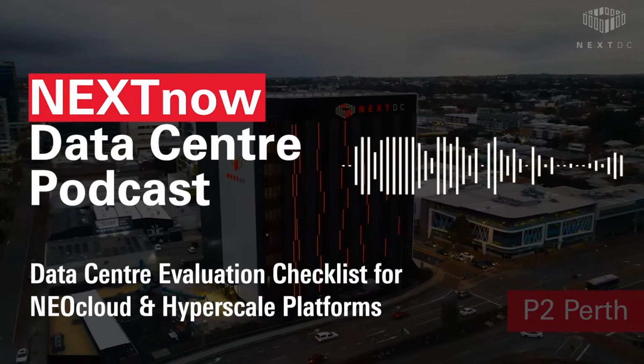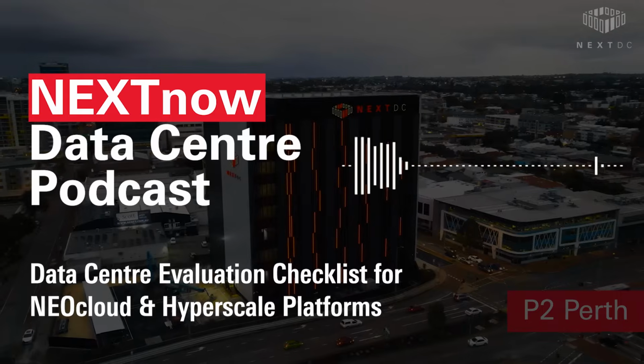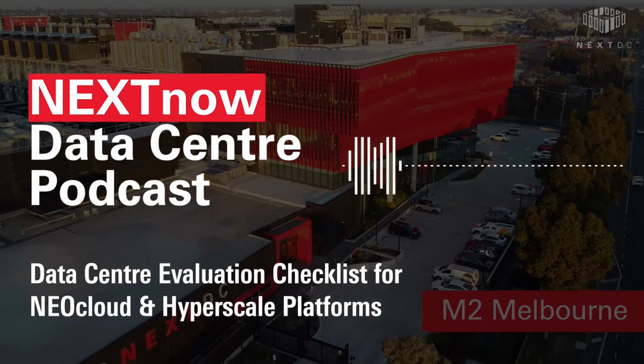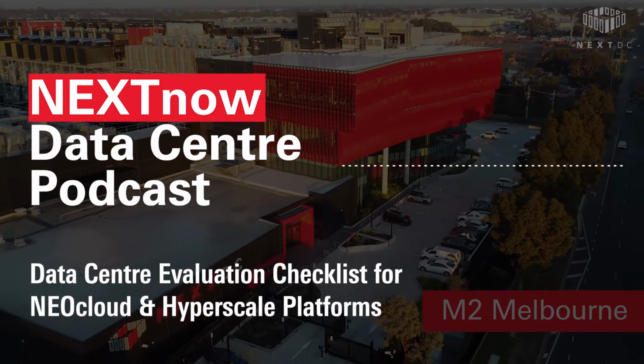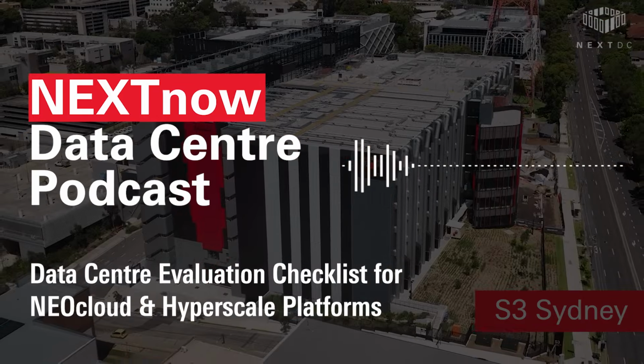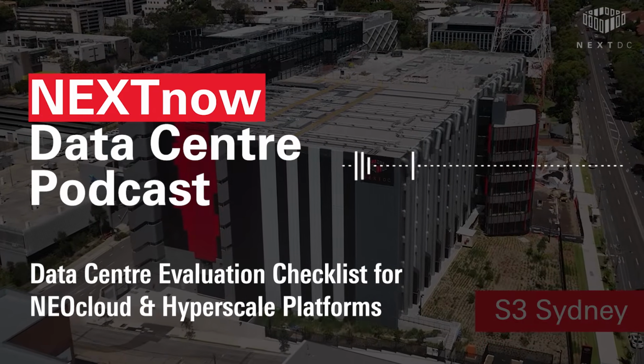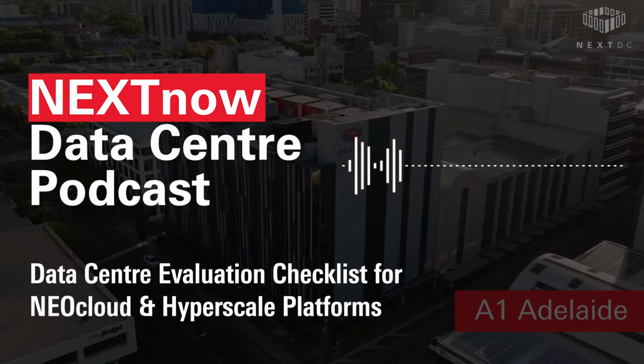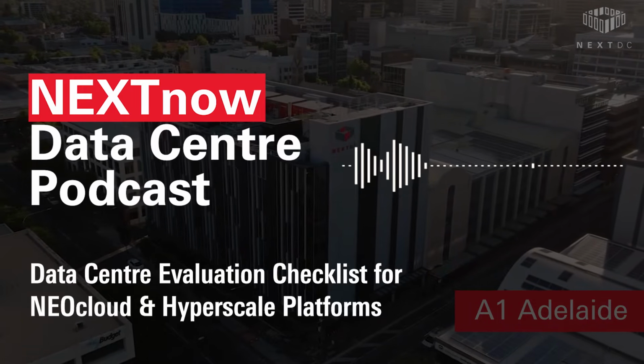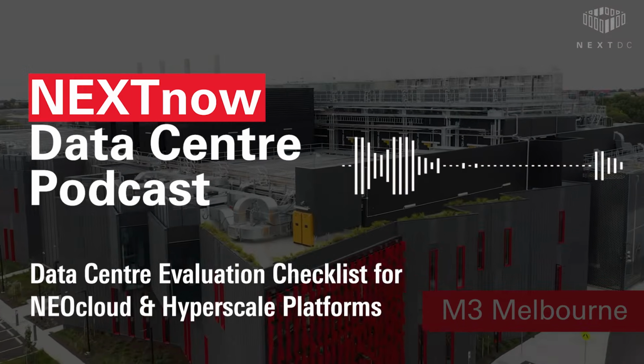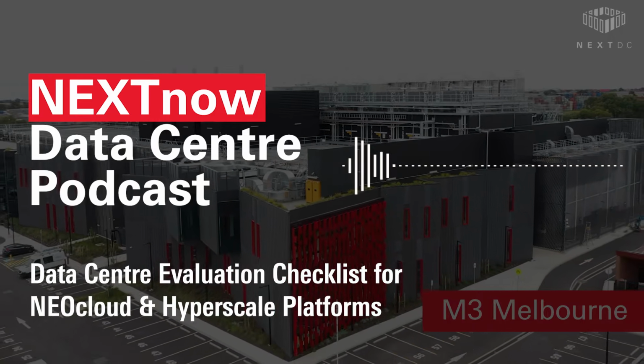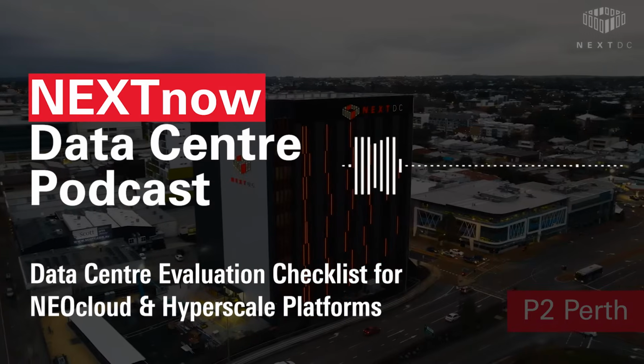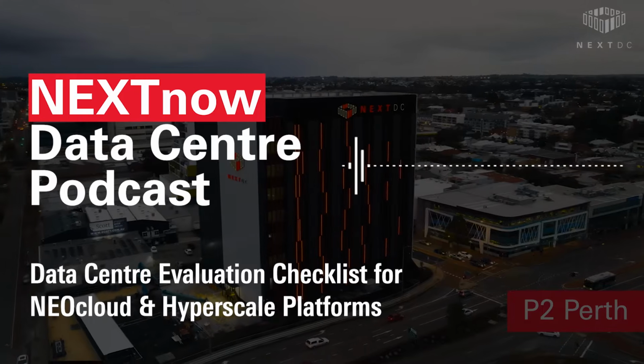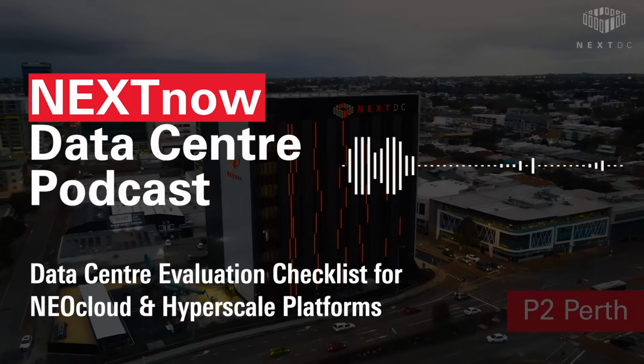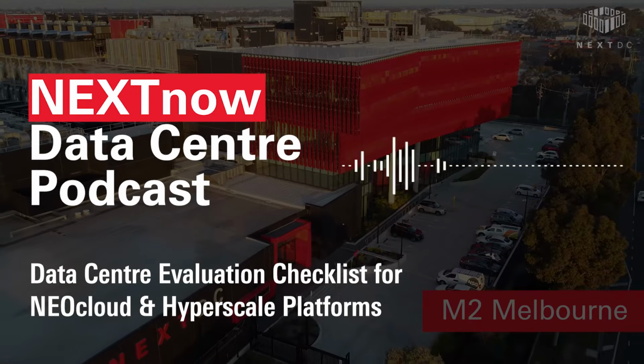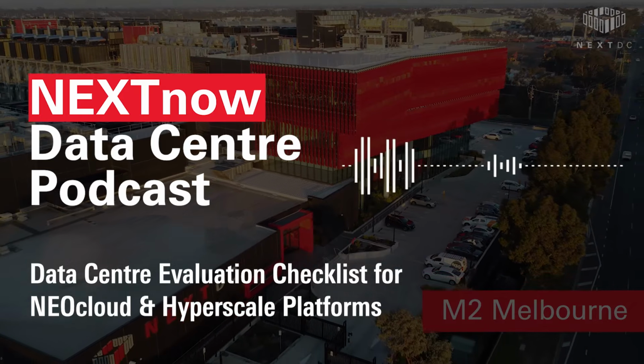Power is only one layer of protection. Fire safety is just as critical. Modern facilities employ very early smoke detection systems known as VESDA, combined with thermal, smoke, and flame sensors for multiple layers of safety. Some sites even integrate outside air quality monitoring with automatic bushfire shutdown procedures, vital for the Australian environment. The best designs include 2-hour fire-rated zones, compartmentalising risks so that even in a worst-case event, your equipment stays safe. Fire protection isn't about alarms, it's about anticipation.